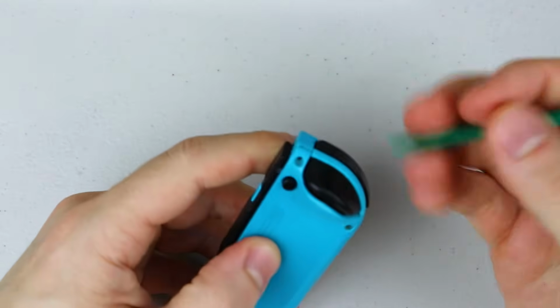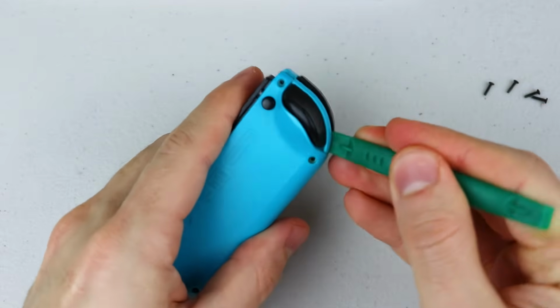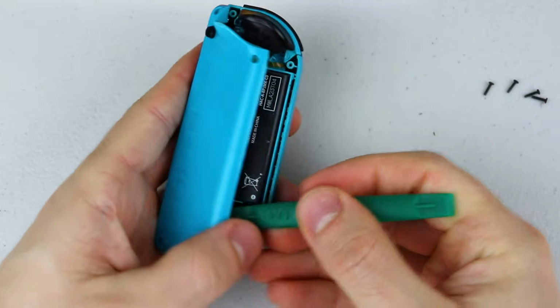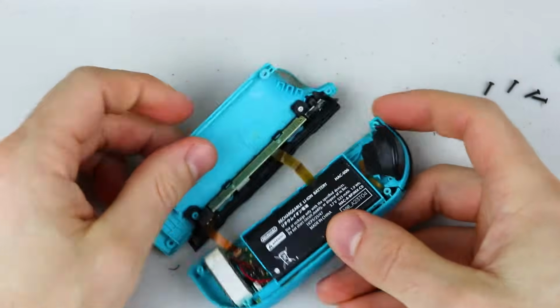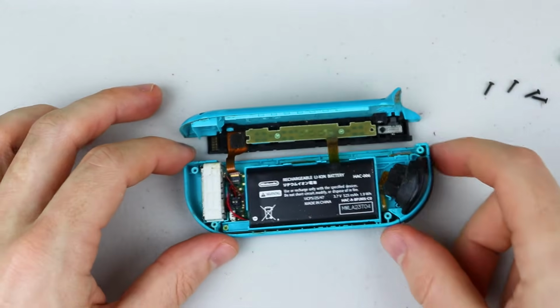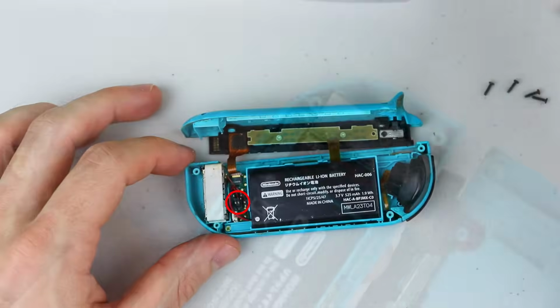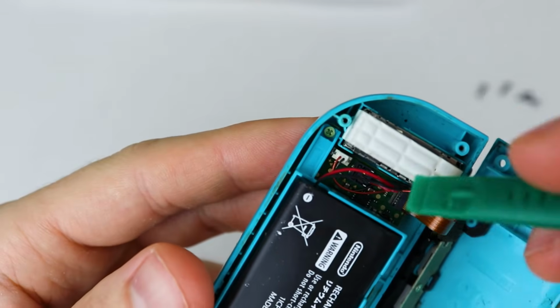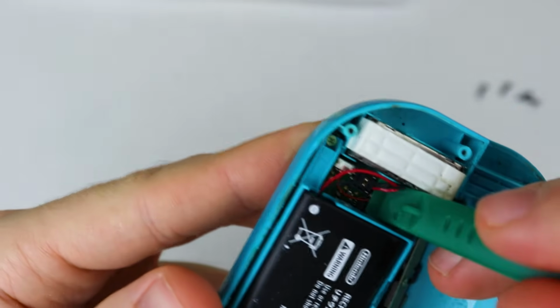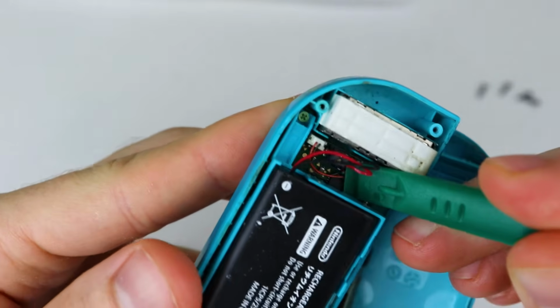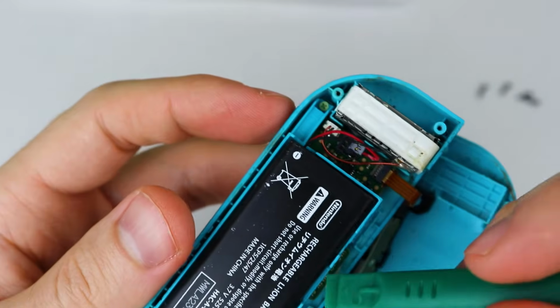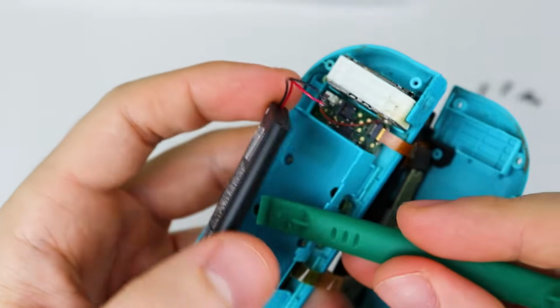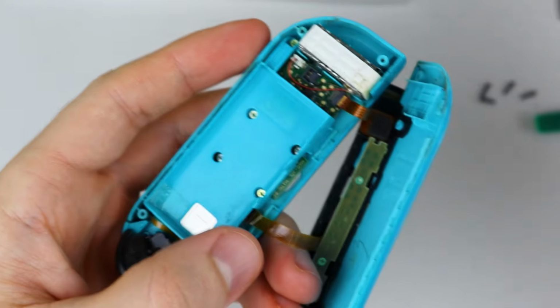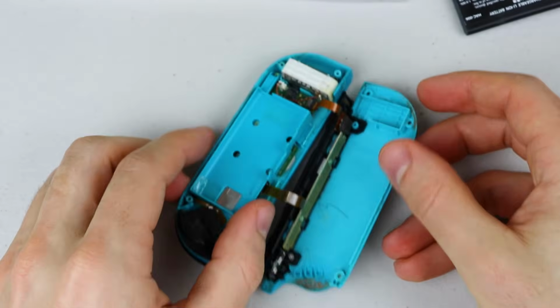And once the screws are removed, we'll carefully pry up the back plate with the pry tool, as there are 2 cables connected to it. The cable to the battery will need to be pried up. One way to do this is to wiggle the green pry tool under it and lift up. Once that's taken care of, we'll then pry the battery off as well. Sometimes the adhesive under the battery is pretty sticky and might take a little more effort to remove, but once removed, we can place it to the side.